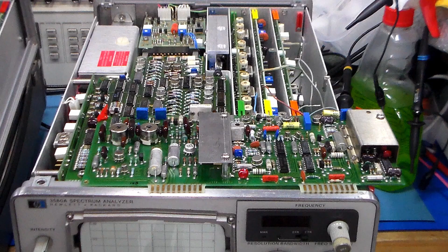This is the A2 circuit board out of the HP3580A audio spectrum analyzer, and one of the minor faults that was occurring was that the tracking generator output from the unit was not giving any sensible signals, and after considerable testing just to try and rule everything else out, it's come down to basically this guy here, U7, which is an MC1496G double balanced modulator demodulator.